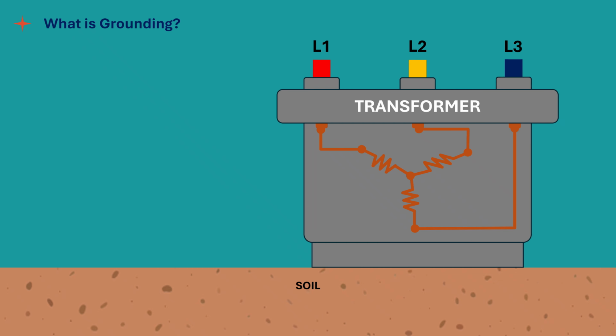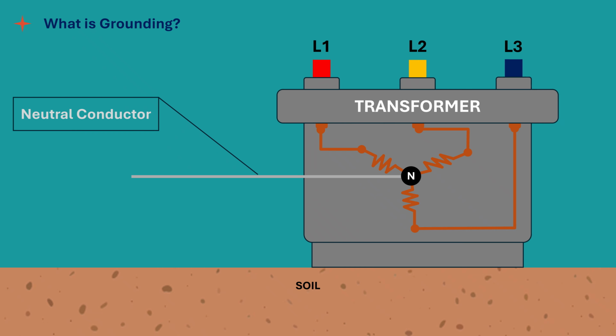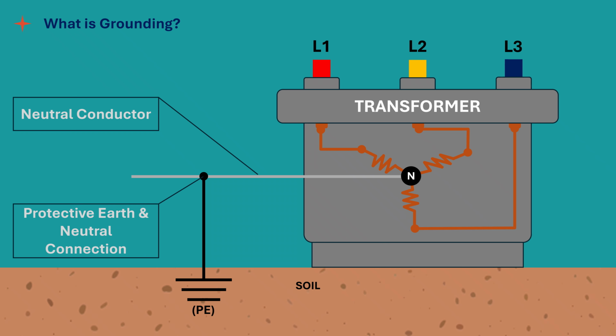Now that we've covered earthing, it's important to understand how grounding differs. Grounding is the intentional connection of a current-carrying conductor, usually the neutral point of a transformer or generator, to earth, which sets the system's reference potential and controls how the system responds during an earth fault. All of these functions work together to ensure the electrical system remains stable, protected, and able to respond safely during faults or surges.